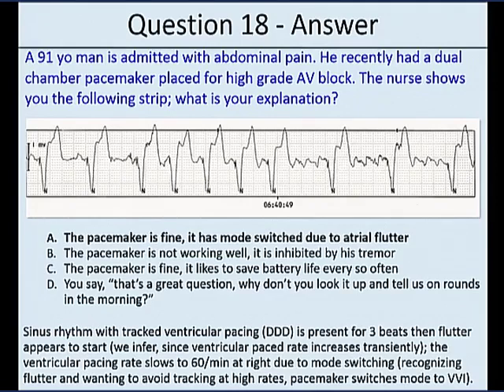I'm not going to be fooled by that. I'm not going to pace every one of those, or even pace in response to every one of those, or even pace at the upper rate limit. I'm going to assume that there's an atrial arrhythmia going on, and I'm going to switch modes temporarily to ventricular demand and not bother with atrial input. And as soon as the rhythm changes back to normal, it reverts back to the dual chamber mode.